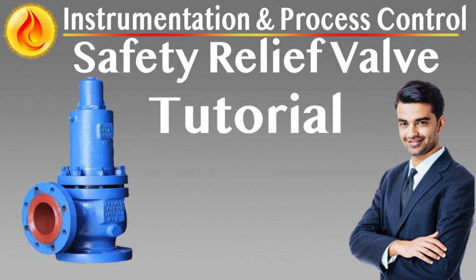Back pressure and valve performance. Built-up back pressure refers to the resistance created in the discharge line once the valve opens. In non-balanced valves, this back pressure acts against the spring force, potentially preventing full lift or causing early closure. When constant back pressure exists, the valve spring must be selected and calibrated to compensate for this constant offset. The spring is set for the difference between the set pressure and the constant back pressure.